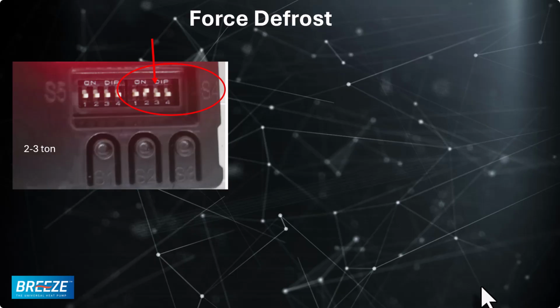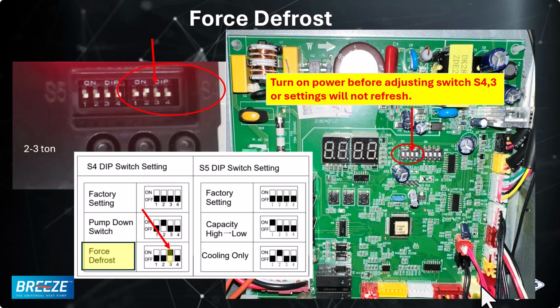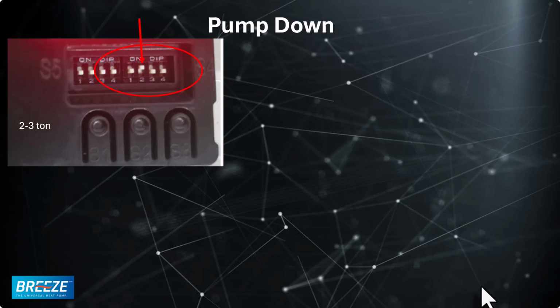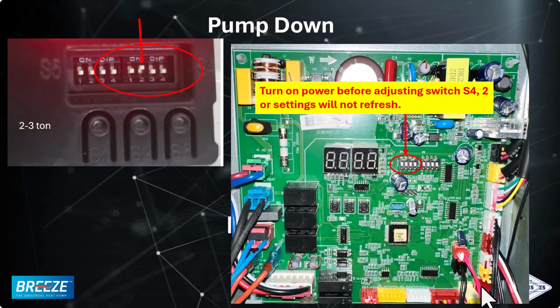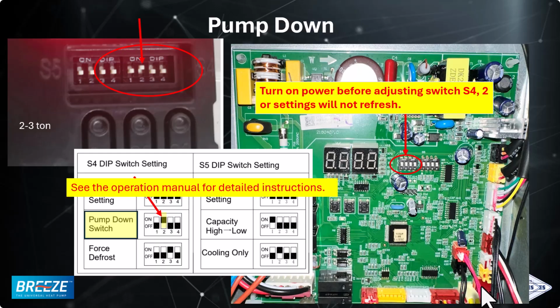Force defrost setting, we're going to go to dip switch bank 4. We're going to change dip switch 3 to on. And before changing this switch, you want to make sure that your power is on. You can also do a pump down on the unit. On dip switch bank 4, switch 2, we'll turn this switch to the on position. There's also more detailed instructions on pump down in the installation manual that you need to know.